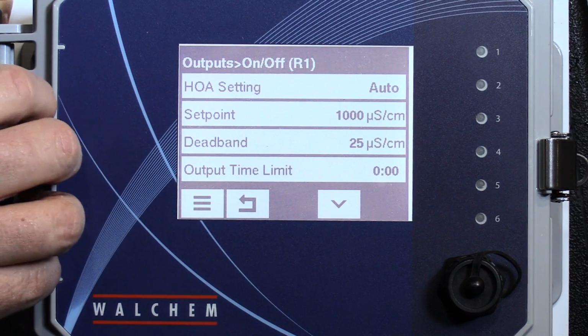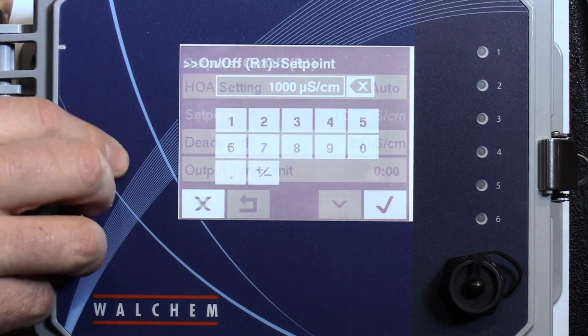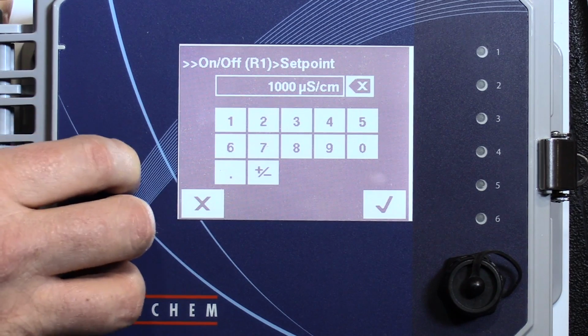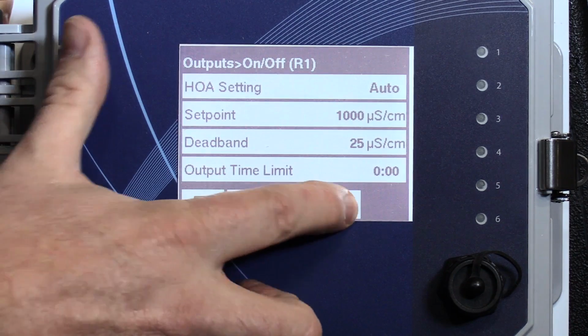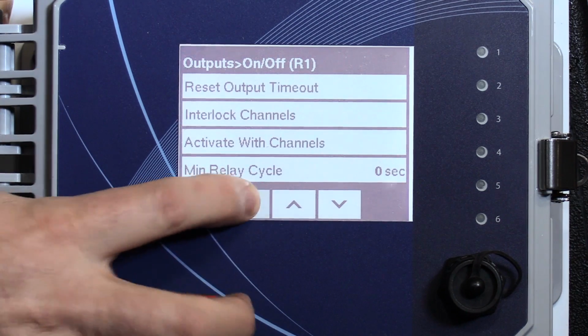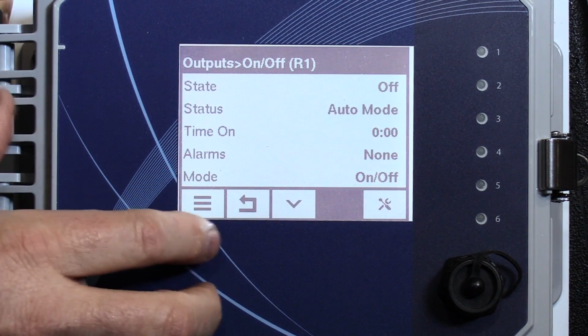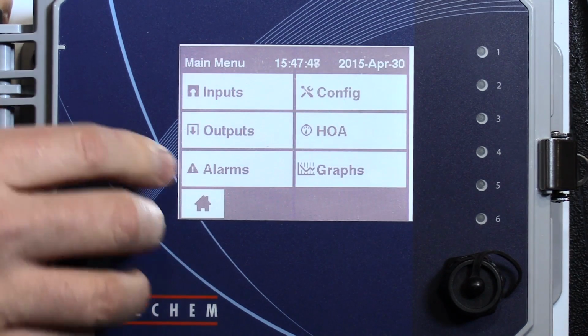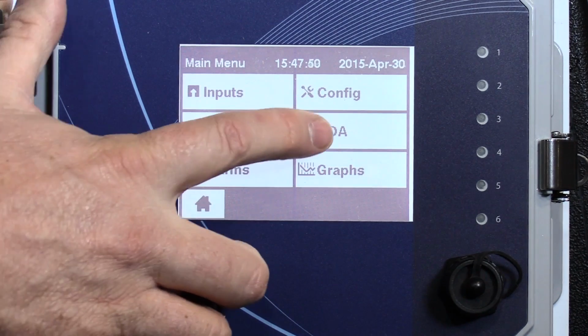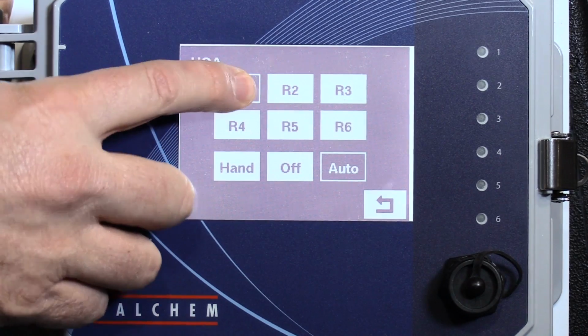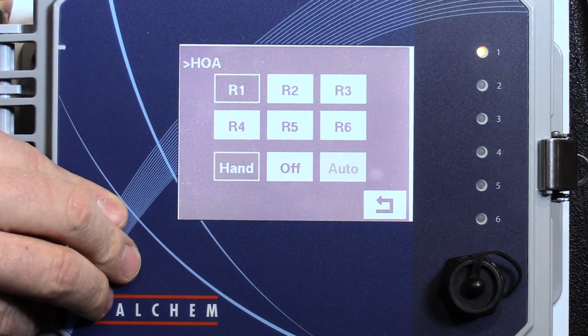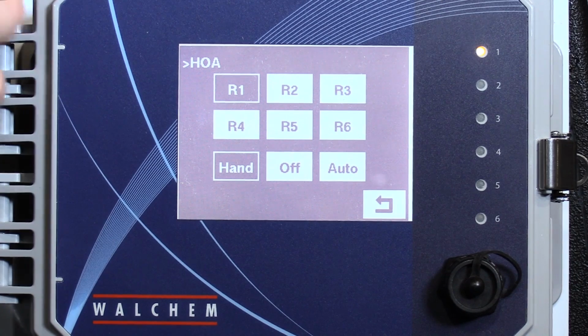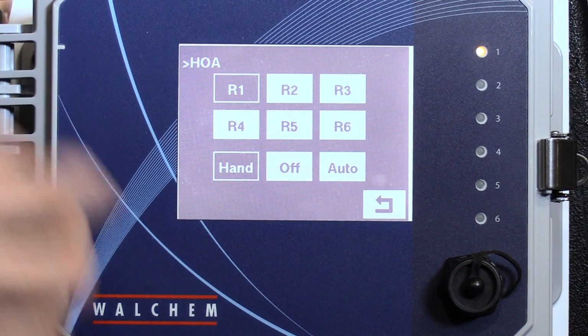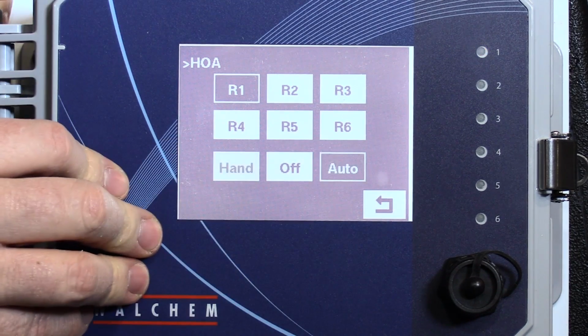All relays are set to off position. You set your set point of what you want your conductivity to be, 1000, you check it. And then you back out. Now you can test the relay to make sure your pump comes on by touching the HOA button, selecting relay 1 and turning it to hand. Light comes on, your pump should come on. Set it back to auto and it will go off.